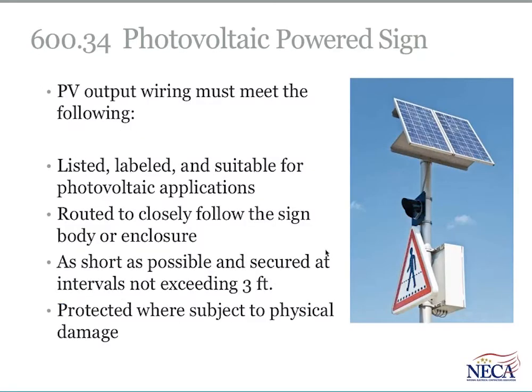There's requirements in there about the output wiring, and of course a listing and labeling requirement is there. Must be suitable for the PV application, so the type of cable that you're using for output conductors is impacted there, and they must be routed to follow the sign body, the sign enclosure, short as possible on the output conductors and protected wherever they're subject to physical damage. And you can see the sign to the left in the image, and some of the output conductors that are making entry into the bottom of that enclosure on the right side of the pole.